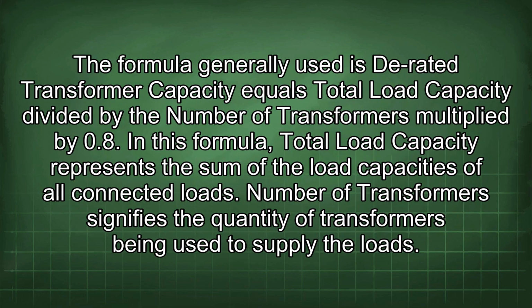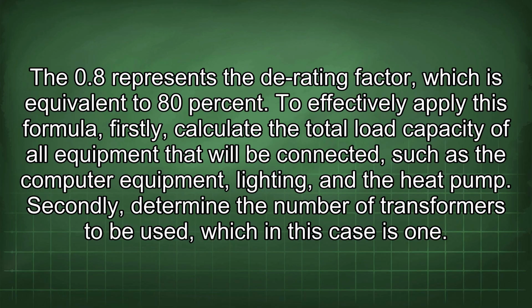The formula generally used is derated transformer capacity equals total load capacity divided by the number of transformers multiplied by 0.8. In this formula, total load capacity represents the sum of the load capacities of all connected loads. Number of transformers signifies the quantity of transformers being used to supply the loads. The 0.8 represents the derating factor, which is equivalent to 80%.